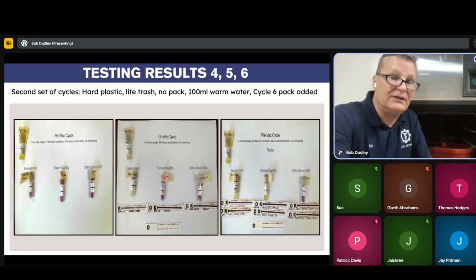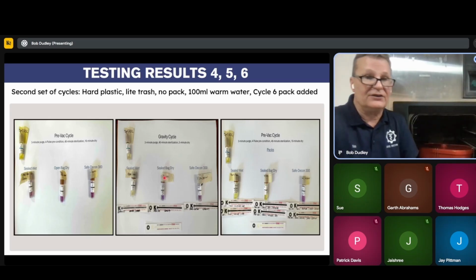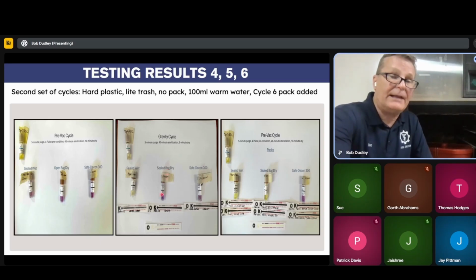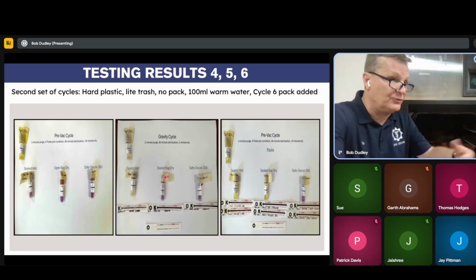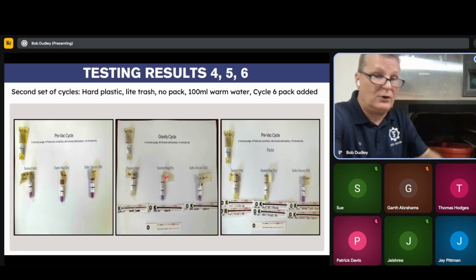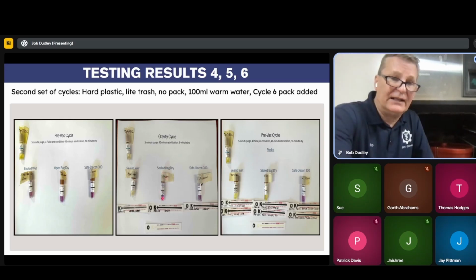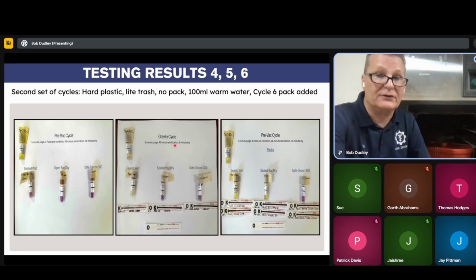With the dry bag, starting on this cycle, I sealed the dry bag but left a hole in the top, which is what a lot of people do. They'll go, okay, we'll just put a zip tie on it, or we'll tie it and leave the hole at the top. So I left about a half-inch hole in the top of this and ran that. So the gravity cycle on the Safe-Decon was good. Sealed bag was good. This bag did bust open a little bit bigger, and we got the kill on it. And again, that was a 3-minute purge, 40-minute sterilization. There was no dry on the gravity.